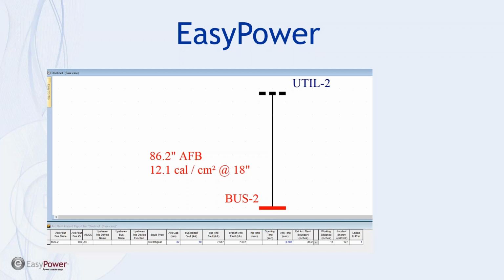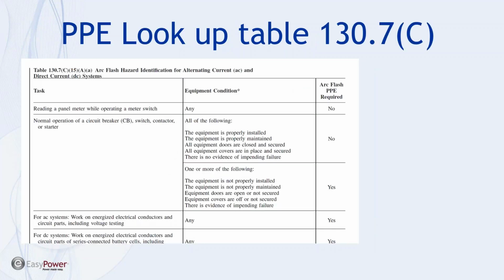So the alternative in NFPA 70E, the alternative to labeling or deciding what PPE we need, we're given two options. One is calculating incident energy, which I've just done and showed. The other is, if we have not done a study, the PPE selection is through a PPE lookup table. So again, this is only applied if we have not calculated incident energy. So that's why we're going through this exercise. Now, I'm not an expert at using the lookup table, but let's walk through this together.